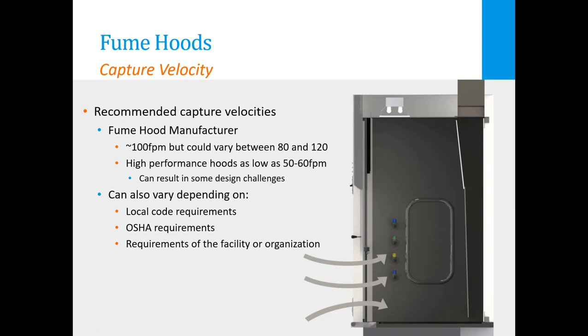While capture velocities can vary from manufacturer to manufacturer and between types of hoods, common capture velocities are typically around 100 feet per minute but could vary between 80 and 120. There are also high performance hoods that can have capture velocities as low as 50 to 60 feet per minute and remain effective at meeting minimum containment requirements. This can result in some air distribution design challenges that we'll address later. Capture velocity may also vary depending on local code requirements, OSHA requirements, or the unique requirements of the facility or organization operating the lab.